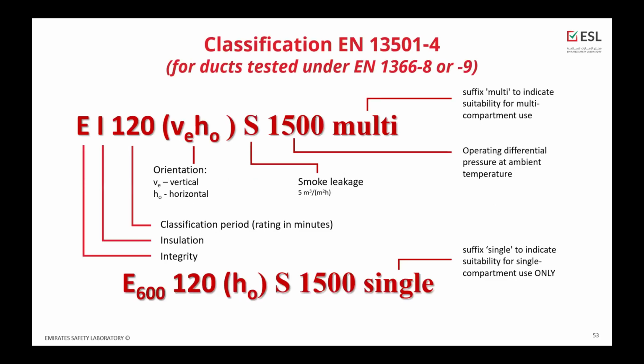The smoke extraction duct classification looks very similar, but instead of orientation, you have two other factors: the operating differential pressure at ambient temperature, and the suffix multi or single, which stands for either multi-compartment use or single compartment use. Also, there is a difference between EI for multi and single compartment, because there is no I, there is only E600, which means that this duct is for the single compartment test under 600 degrees.